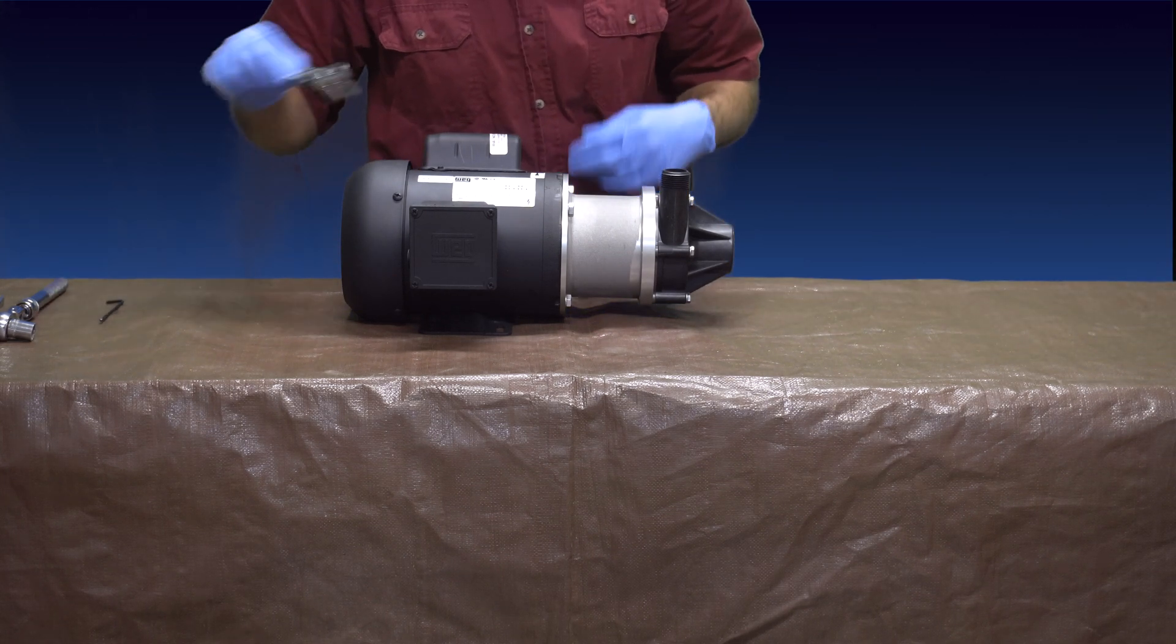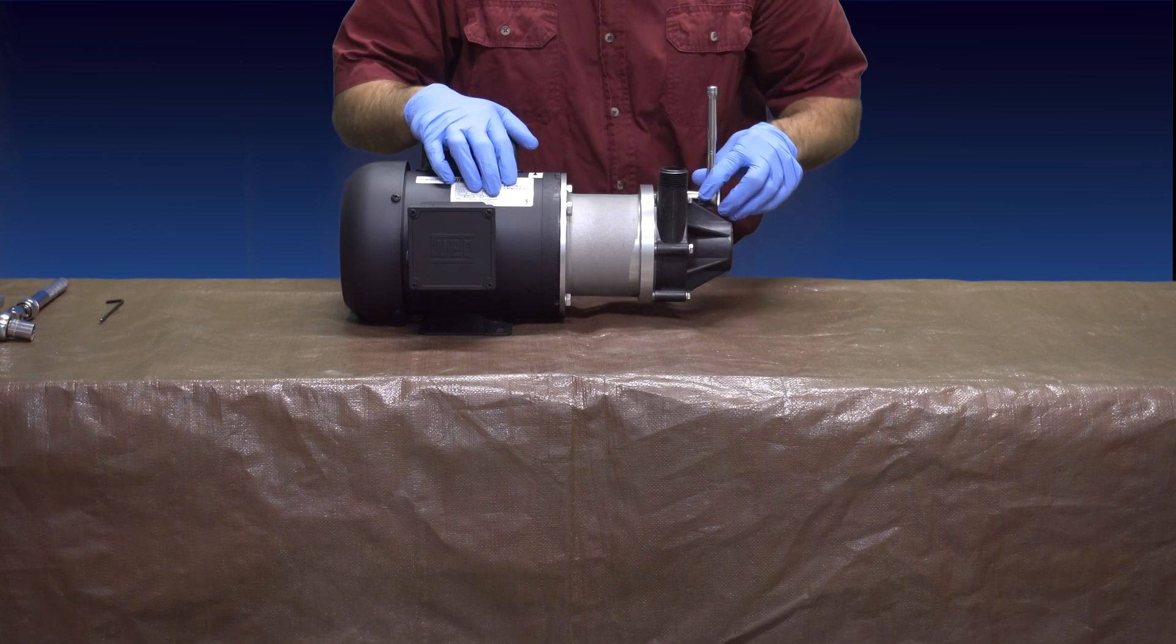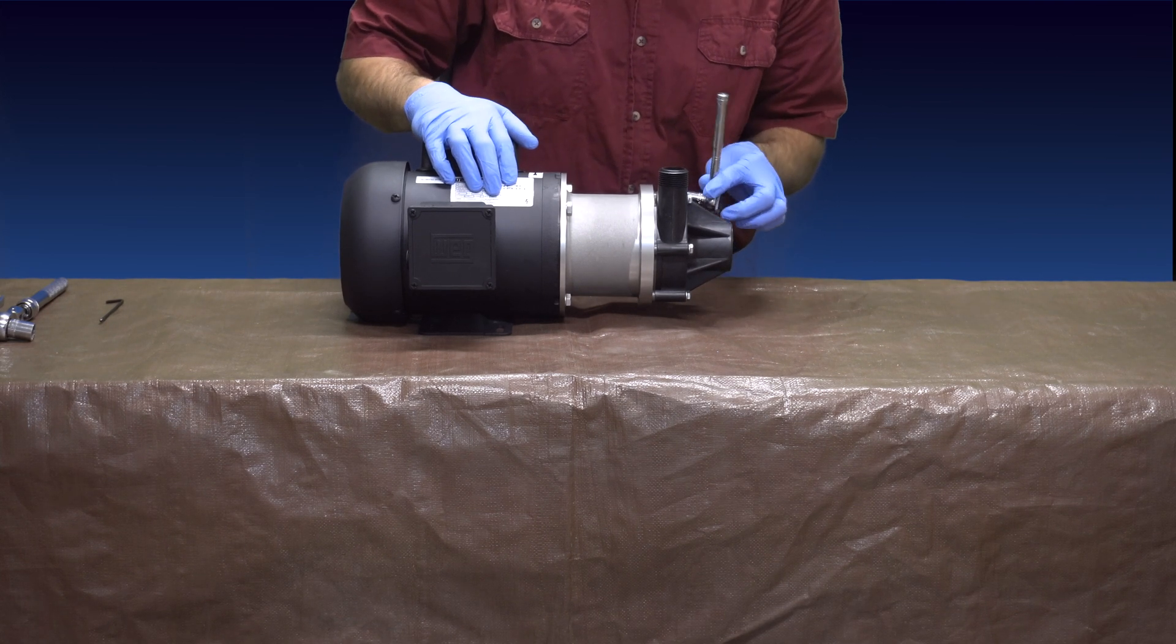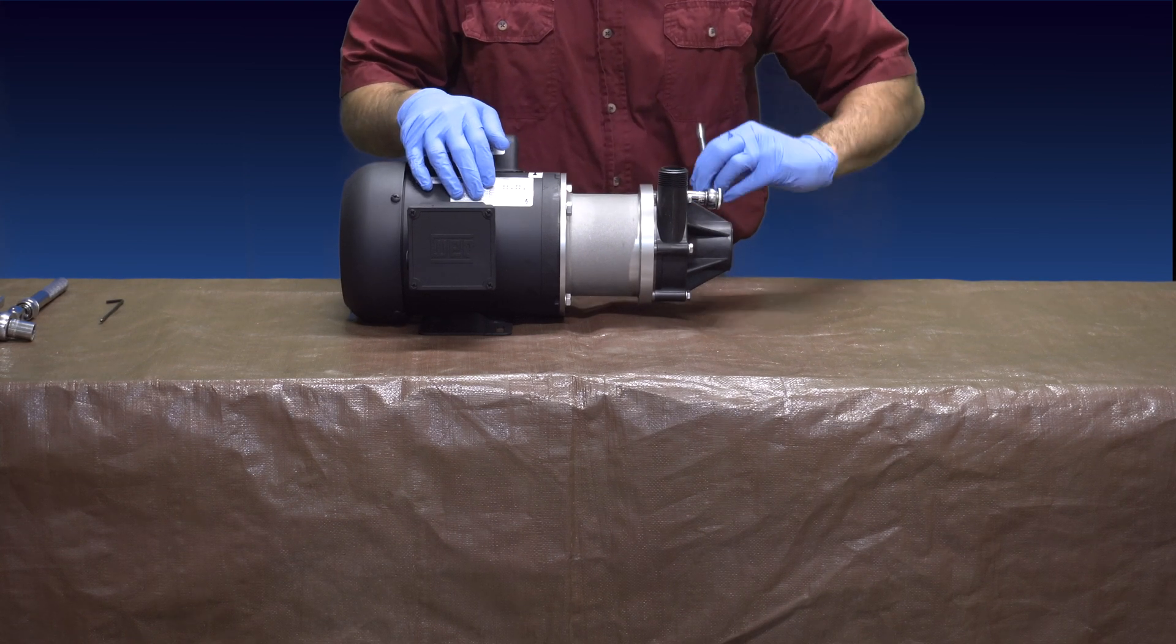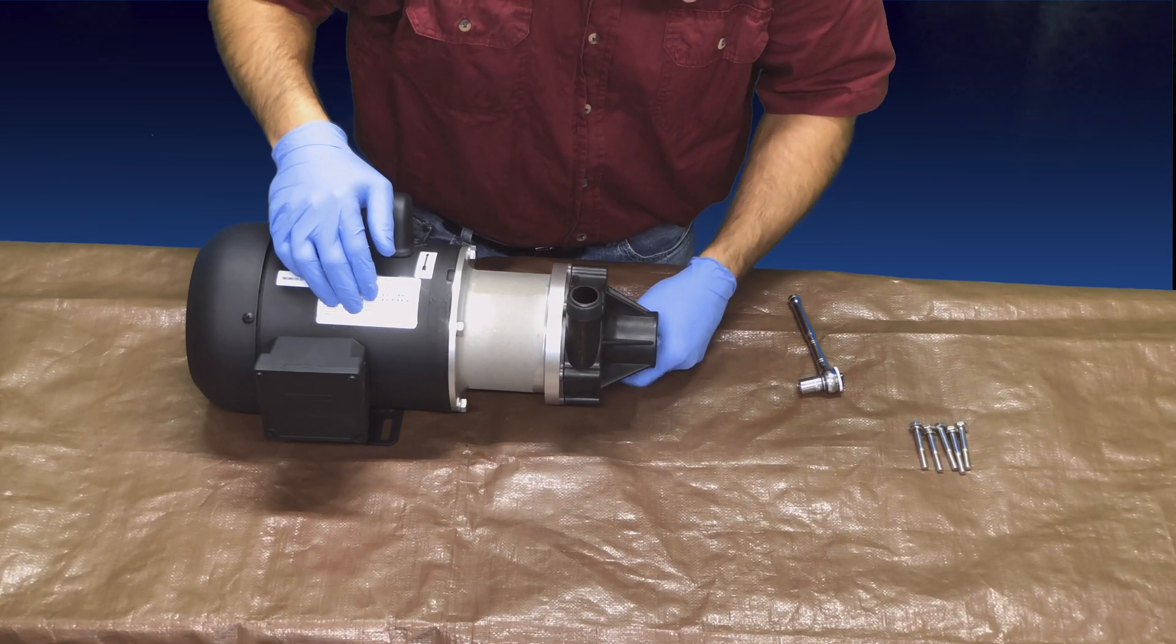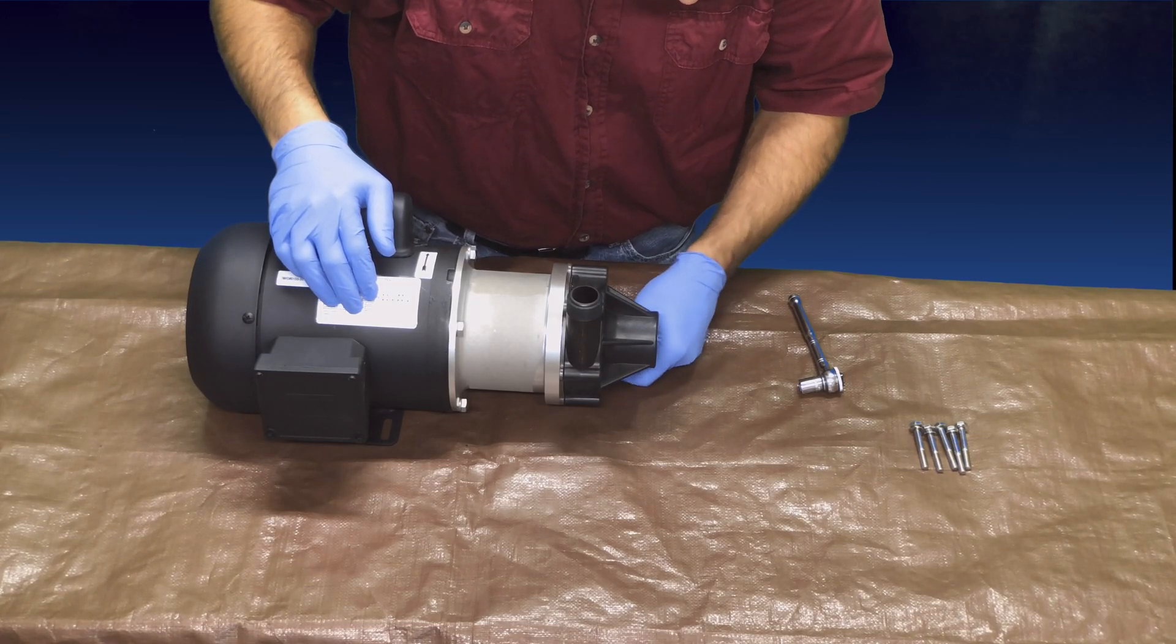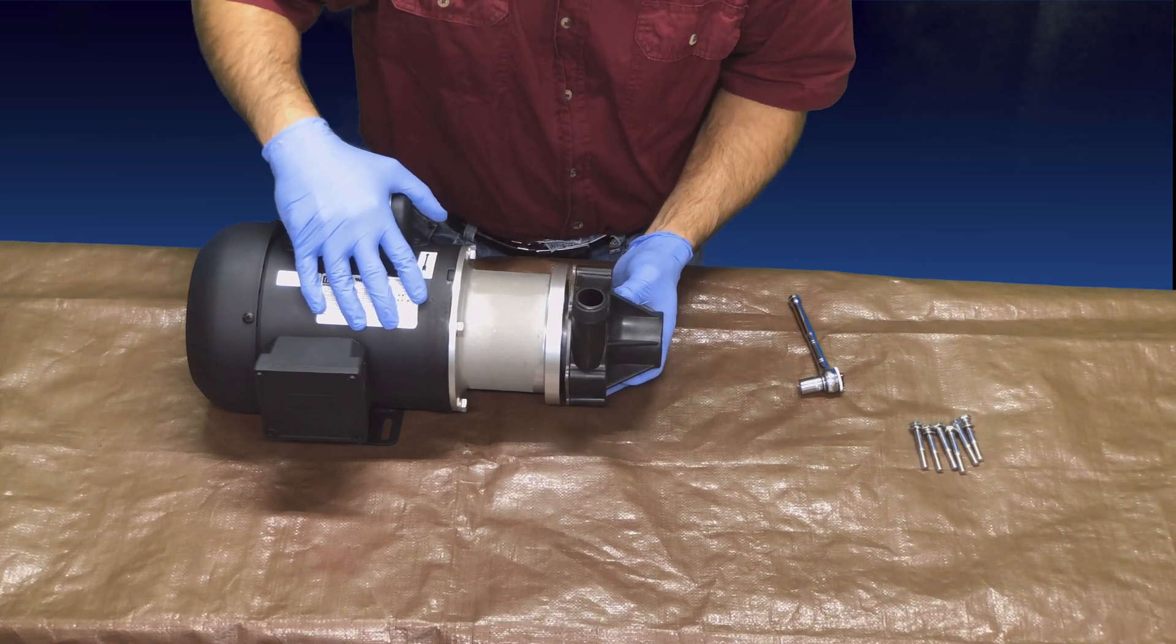The pump assembly consists of a drive end section and a wet end section. We are going to start by removing the components of the wet end section from the drive end section. Use a 7/16 inch wrench to remove the six screws holding the wet end to the drive end. Now the wet end can be removed by pulling it straight out. You will need to pull firmly because you are also separating the magnetic coupling when performing this step.